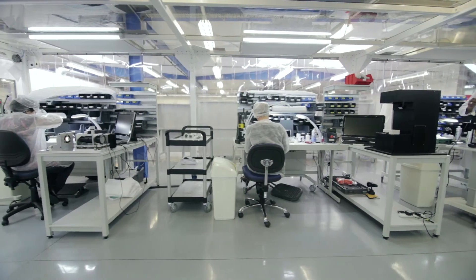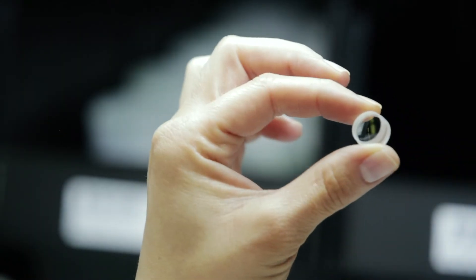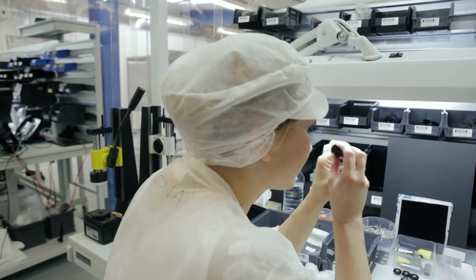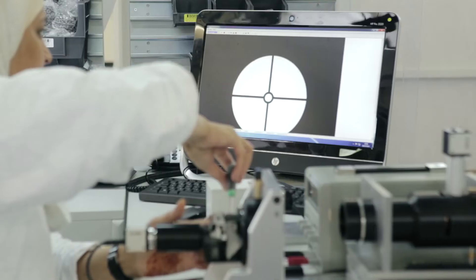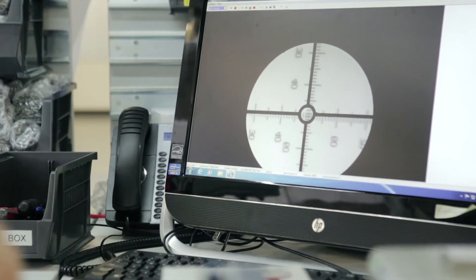Our slit lamp is handmade here in Windsor. Production flow starts in the clean room itself and goes through the various stages of the assembly process. This ensures maximum cleanliness and high quality optics up to the point where sub-assemblies are built on jigs, and finally each one is tuned to optimise optical performance.